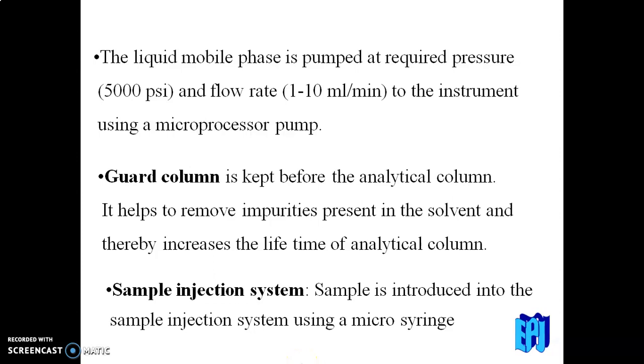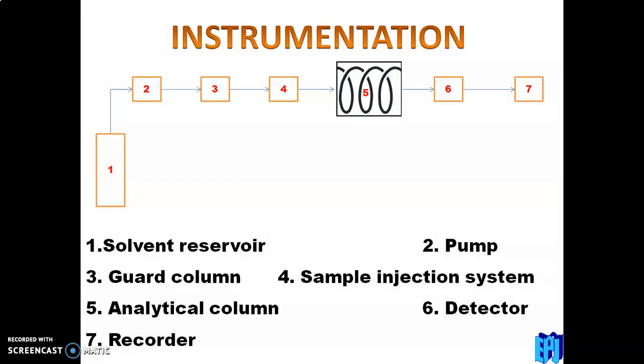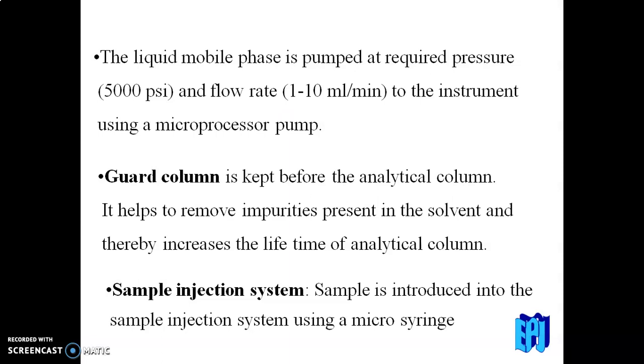The liquid mobile phase is pumped at a required pressure of 5000 psi and a flow rate of 1 to 10 ml per minute, using a microprocessor pump. The function of the pump is to deliver the solvent at the required pressure and flow rate.